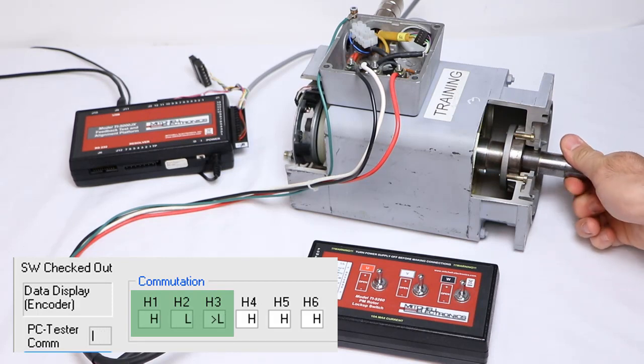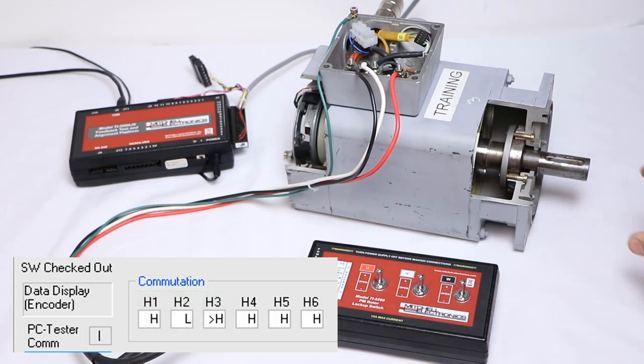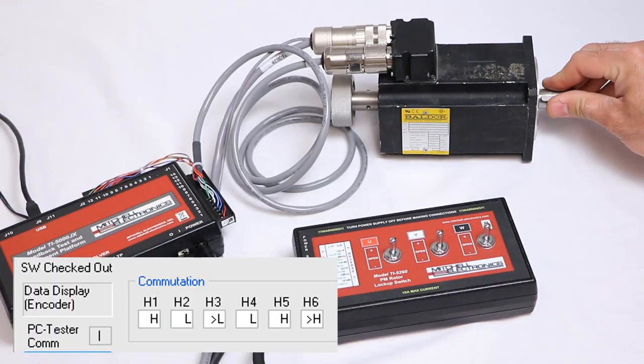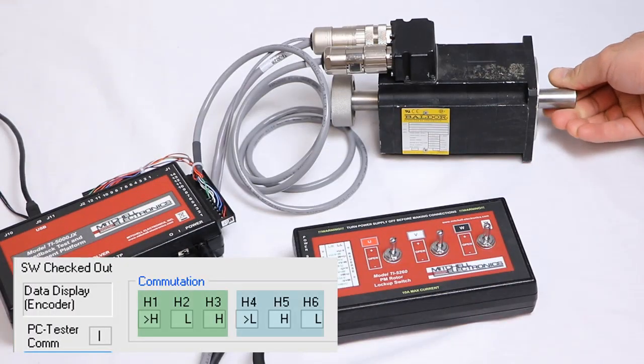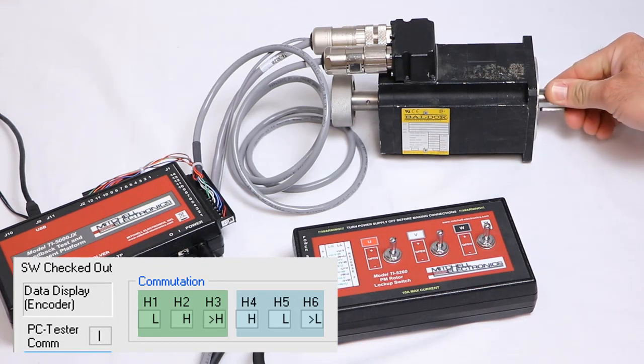The caret symbols show the last signal to have changed. If the commutation feedback has complement lines, then make sure that all six signals are changing, and that H4 through six are exactly opposite of H1 through 3.